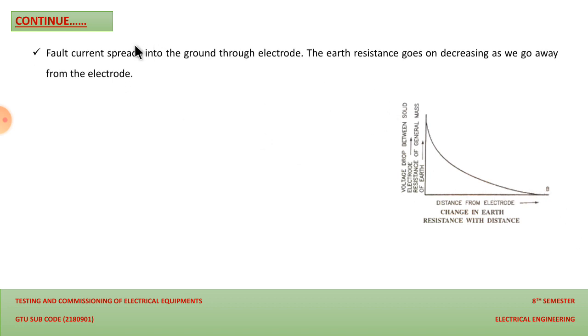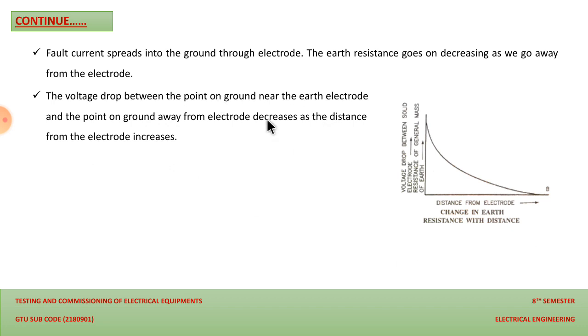And the fault current spreads into the ground through the electrode. That is obvious, since the soil has ground potential, or we can say zero potential. So the heavy current which transfers through any equipment is discharged through the ground, and the earth resistance goes on decreasing as we go away from the electrode. That is shown in this diagram. And the voltage drop between the point near the electrode and a point on the ground away from the electrode decreases as the distance from the electrode increases. That is shown in this graph that we have already discussed.